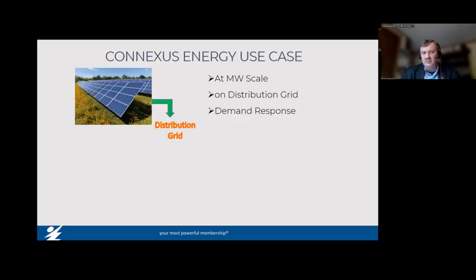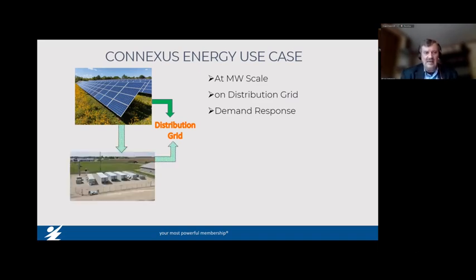So what we did: first we built the solar system, well, we built it all at the same time. The solar system can stand on its own, so we built the solar facilities and that ties and feeds directly into the distribution grid, serving members. Then we built the battery site. The batteries need the solar, and I'll go into some of the contractual obligations for this in a bit. But what we do is, when we want to dispatch the batteries for demand response, we charge the batteries from the solar system. Then when we're hitting the peak time of day, we dispatch the batteries, sending that energy out into the grid, therefore lowering our grid load during peak time.